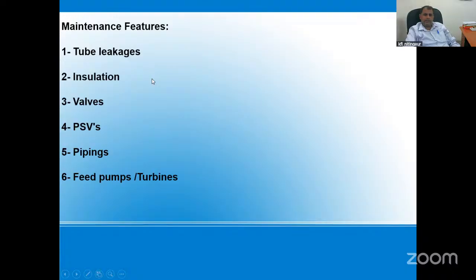Second one is insulation. The boiler furnace, where the combustion is taking place, is duly insulated inside. This is to avoid the heat transfer from the inner side to the outer side. And the inspection of the insulation is very, very necessary. Otherwise, proper efficiency we cannot get.